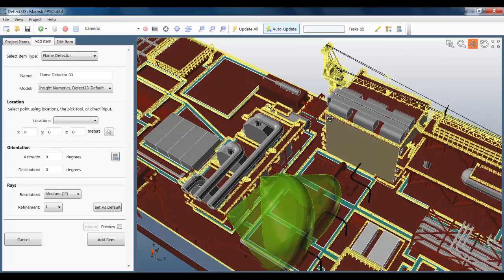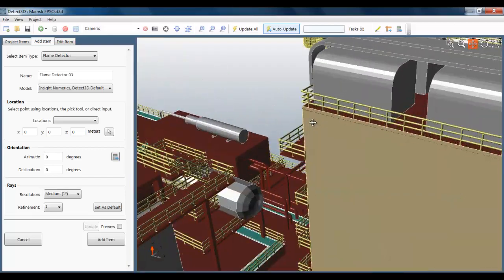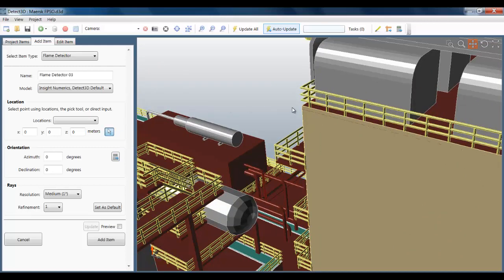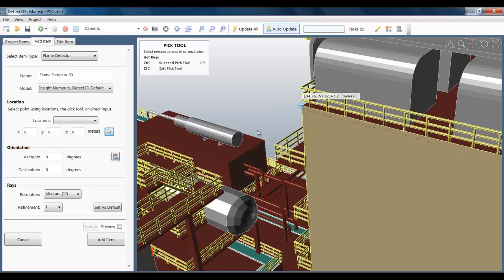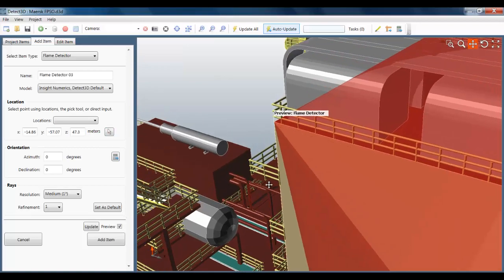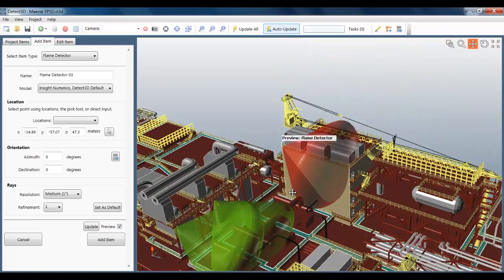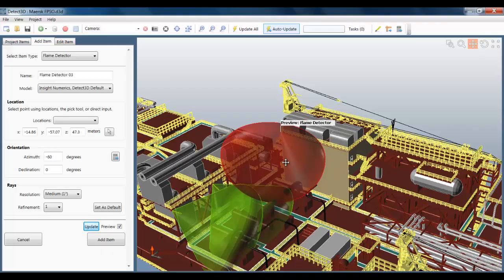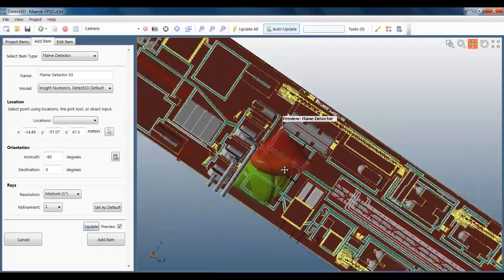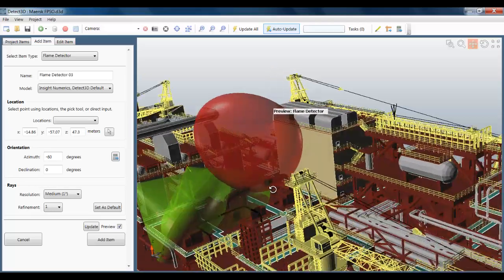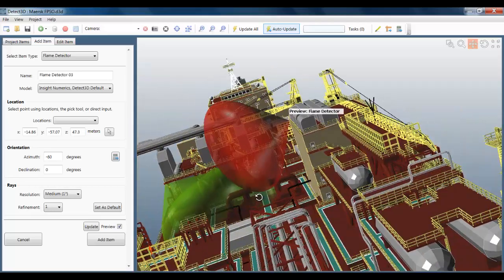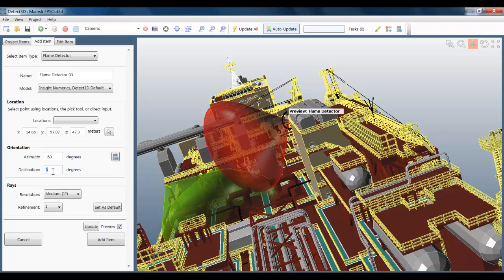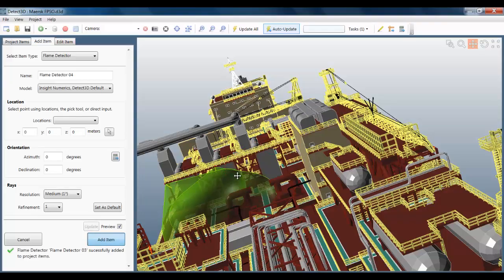And now we're interested in this area, so I'm going to add two more flame detectors at the corners of this building. I'm going to try and get a lock on those coordinates first. If I preview that, I can see that it's pointing completely the wrong direction, but I can change that. If I set the azimuth here, looks better. And now I'm going to have to set a much steeper declination angle because the detector is much higher. So if I set that to 45 degrees and click update, that looks good. So I'm going to add that to the project.